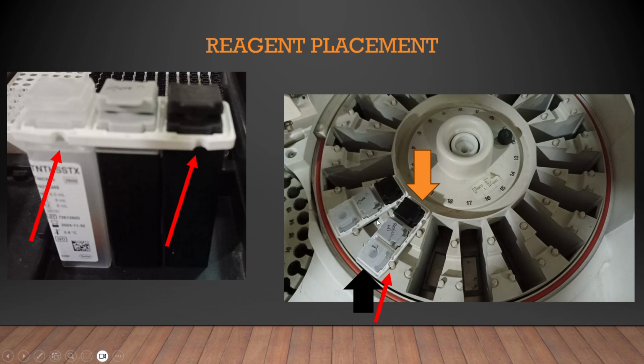Okay, so when you are placing these reagents, this black colored one should always be inside. Okay, see, this is very important. The black colored ones should always be inside the ring, whereas the bead or this white colored one should always be outside. In that fashion only it should be kept. And when you see it, you can see that it has got a small hitch here, right? So they should get fitted properly. Okay, so in that way only it will fit. Now this is very important, because when it is trying to open the cap, there is a mechanism through which it will hold these things and open the caps. If that is not followed, the cap gets stuck, everything gets stuck, and the instrument will stop. Okay, so you have to keep black color inside, the white color outside.